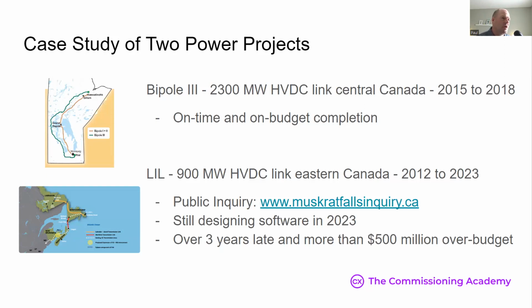Contrast that with our approach on Bipole 3. We had a 6-month period of dedicated integrated factory acceptance testing. There were 60 cubicles required on the project, 30 in the northern terminal and 30 in the southern terminal, and we had all 60 of them in the factory in Germany. They were all wired up together, fully powered and integrated with the full HMI systems, and we could simulate the entire 2300 megawatt power transfer on the systems.